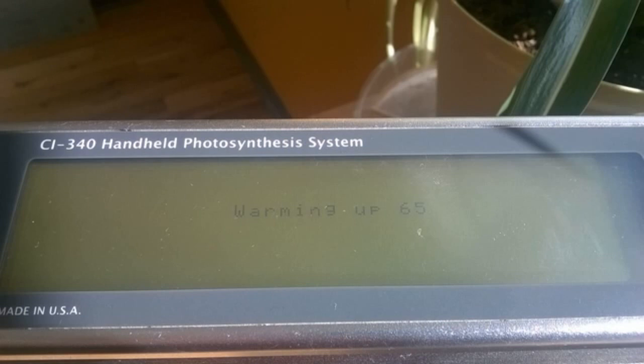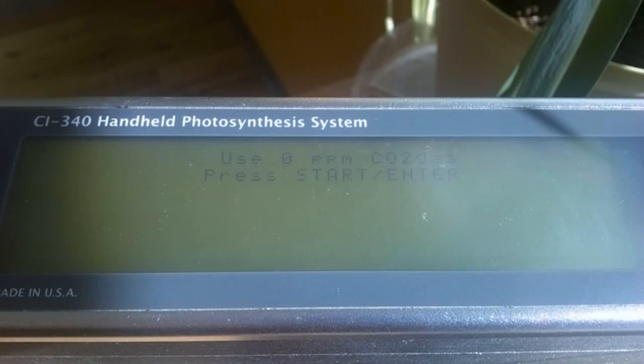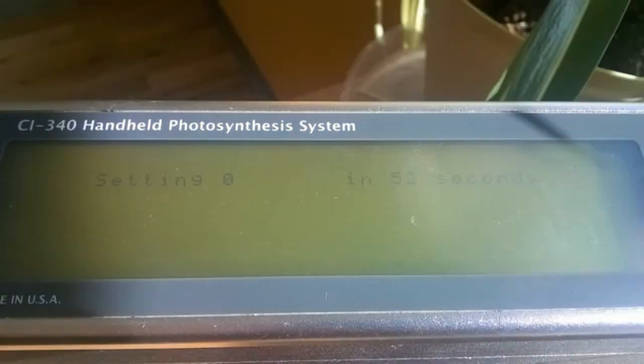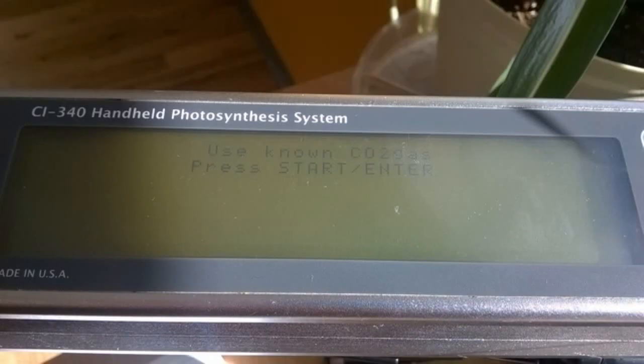You will see Start to set 0, else exit. Hit Start. You will then see Use 0 ppm CO2 gas. Press Start Enter. Setting 0 in 60 seconds will be displayed and the instrument will count down from 60 seconds to 0. At this point, the CO2 concentration of the gas passing the analyzer is taken as 0 ppm and the sensor is calibrated to read this level as 0.